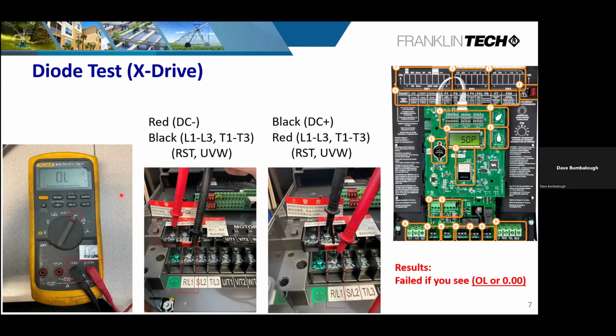What I mean there is similar to a car battery. You have a plus and a minus. The plus is usually referred to as the red conductor, and the minus, the negative, so to speak, is referred to as the black lead. As that's connected properly on your meter, the way you conduct this test is opposite when it comes to the polarity, because it's an electrical check valve that we're actually testing. This is a diode test. We're checking to see if the drive has been compromised on the input side or the output side.